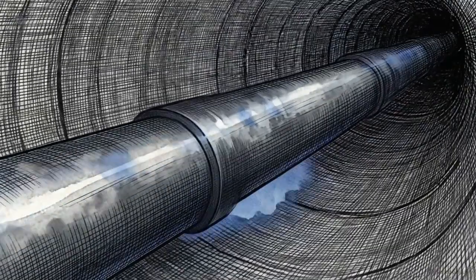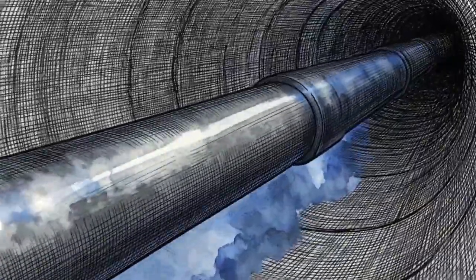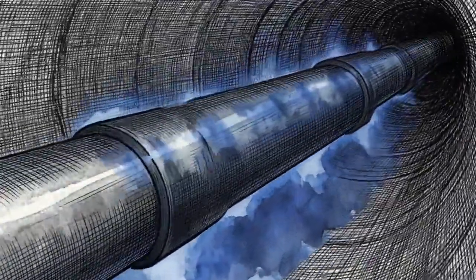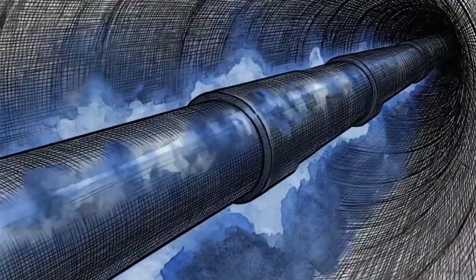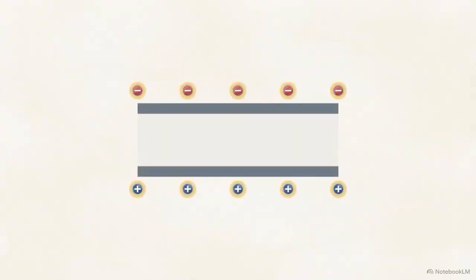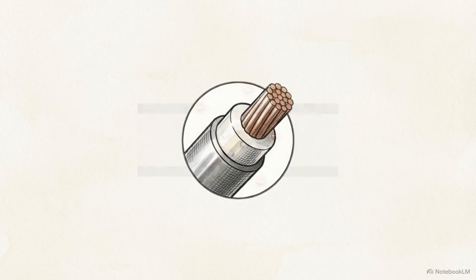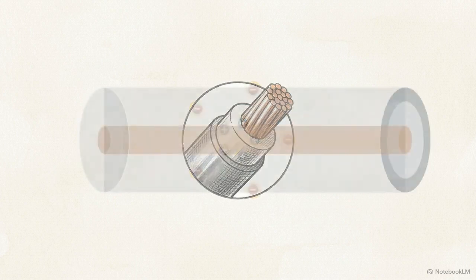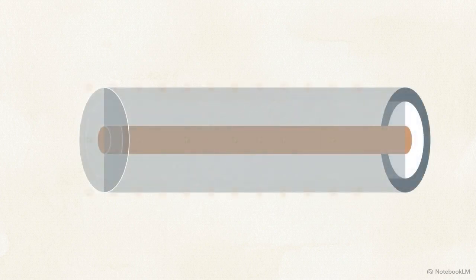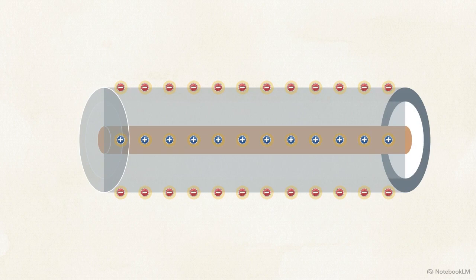But wrapping a high-voltage wire in tight layers of insulation and metal shielding introduces a severe invisible problem: capacitance. Capacitance is essentially the ability of a system to store an electrical charge. It happens anytime you have two conductive materials separated by an insulator. In an underground cable, the inner core and outer metallic shield act as those two conductors. Packed mere inches apart over miles of distance, the entire cable transforms into a continuous capacitor.